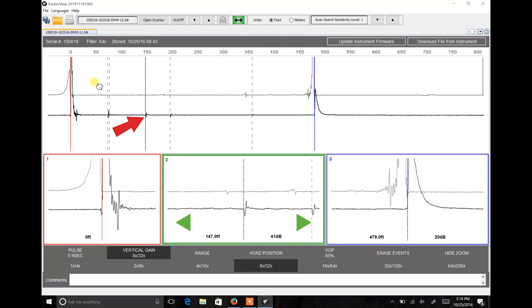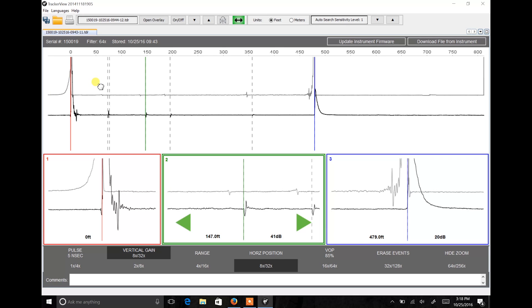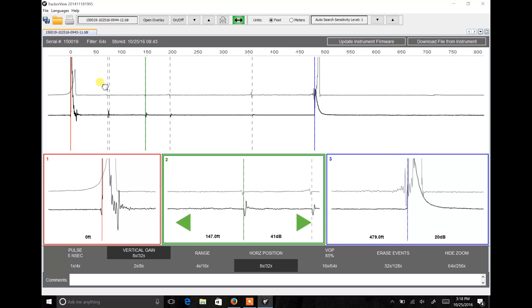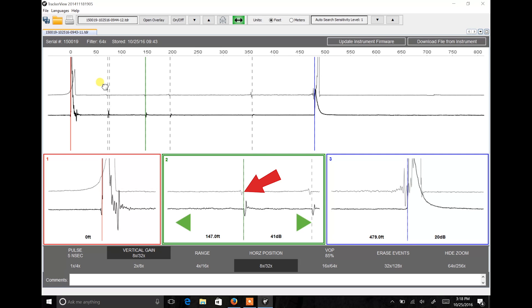Then I'll pick an event on the primary waveform and place cursor 2 on the event and then adjust the overlay to align with that event. Please note that you always want to measure to the leading edge or the left-hand edge of an event on your primary waveform, but on a mirrored overlay, you want to measure to the right-hand edge.